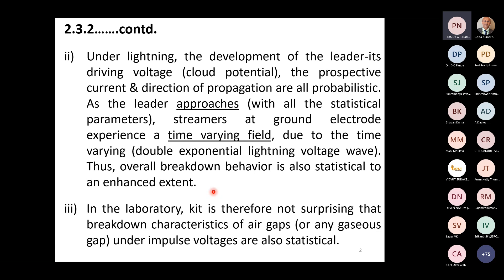I'll show you some figures of the time variations. In the laboratory, remember, it is. It is therefore not surprising that breakdown characteristics of air gaps or any gaseous gaps under impulse voltages are also statistical. What I mean is that even a simple rod gap behaves in a highly statistical manner. If it is an ESE rod, the statistical behavior, according to them, reduces drastically. But it may not at all, because another set of experiments by Nijdam and others have shown that some amount of excitation is not at all helpful. In fact, it may reduce the velocity of propagation because the field at the tip is reduced.